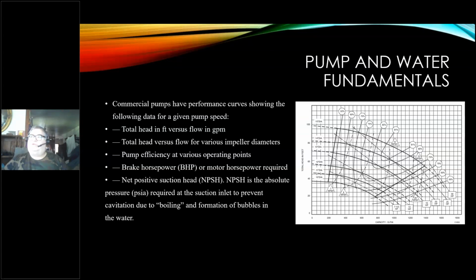Now that full speed could be 3,600 RPM, 1,800 RPM. You have to look at the curve you're looking at to see which speed we're talking about. That's critical. So you need to make sure that you've got the right pump speed first off for the pump you're looking at. Total head versus flow in GPM. Again, the flow is across the bottom, the head is in the vertical. Total head versus flow for various impeller diameters. Again, we've got 1, 2, 3, 4, 5, 6 impellers on this curve.